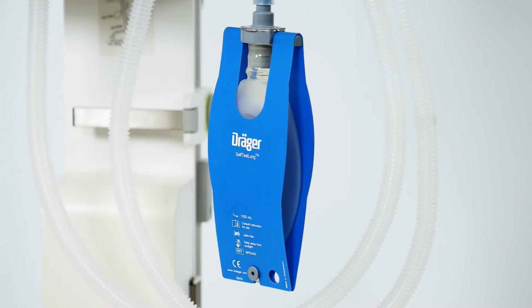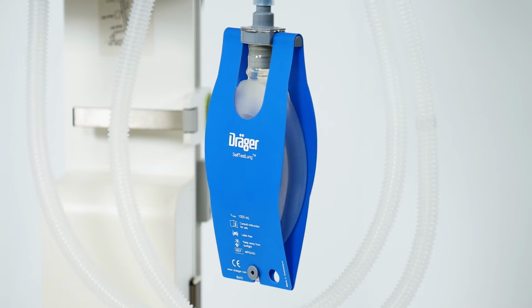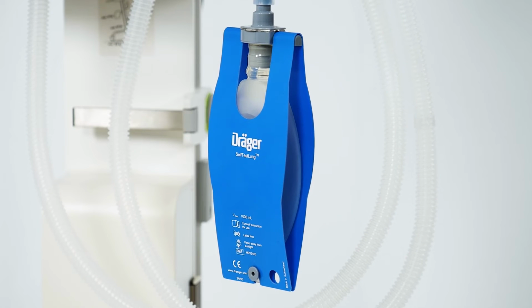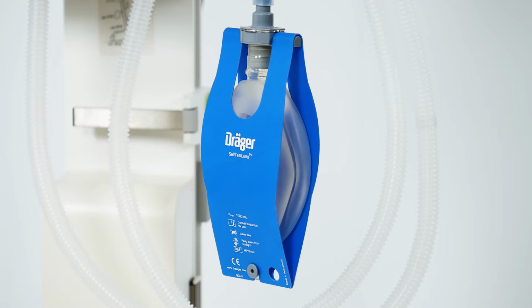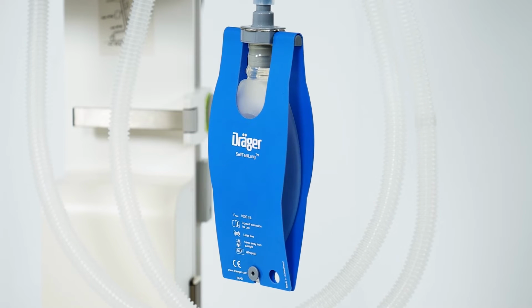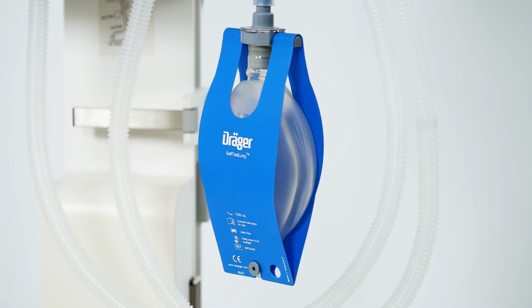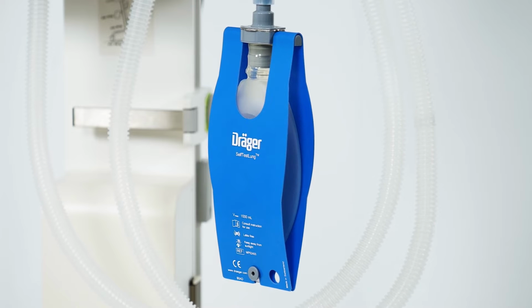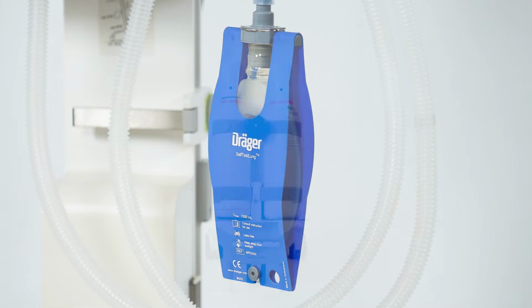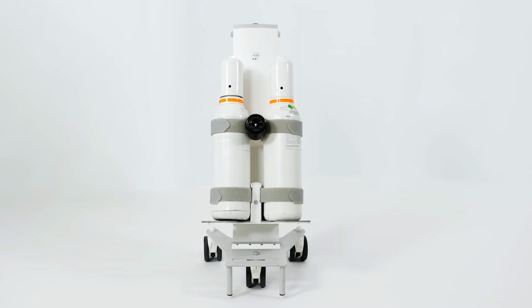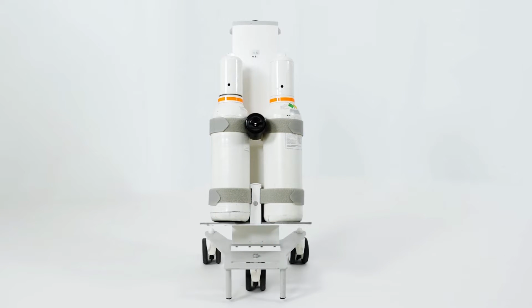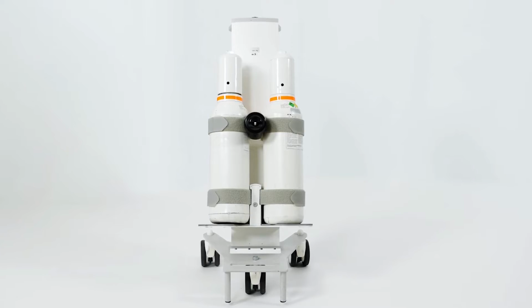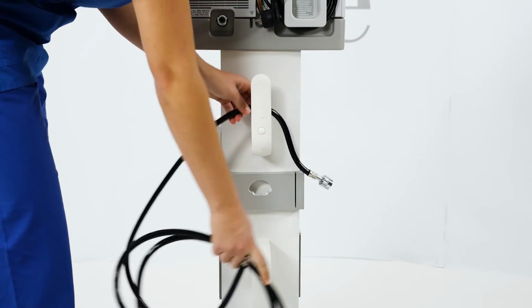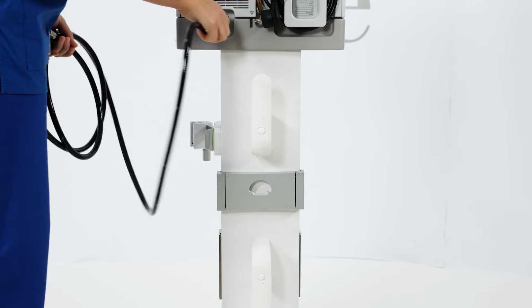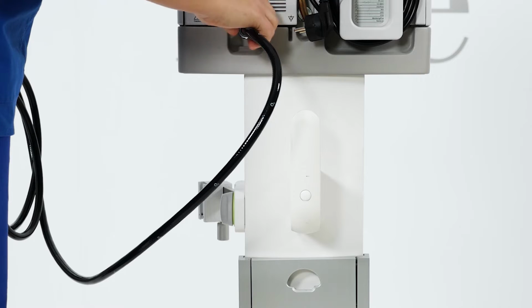For ventilation, Savina 300 Select uses ambient air, which is supplied by an internal turbine. In the high-pressure oxygen mode, O2 supply is provided by a central gas supply system or by compressed gas cylinders. In the low-pressure oxygen mode, O2 supply is provided by an external low-pressure oxygen source, for example an O2 concentrator. For supplying from compressed gas cylinders, Savina 300 Select can be equipped with a transport supply unit or a cylinder holder. For O2 supply from a central gas supply system, connect the O2 compressed gas hose with the O2 connection of Savina 300 Select.